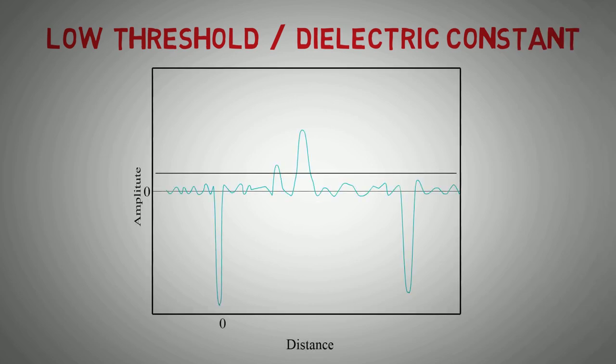A threshold that is set too low can cause noise above the product level to be detected as a false level reading.